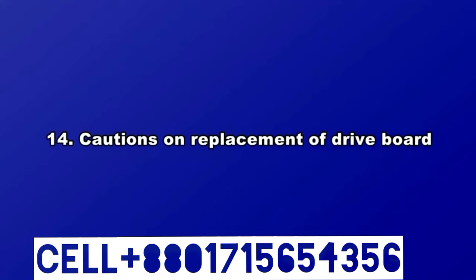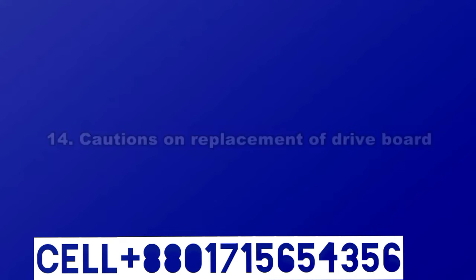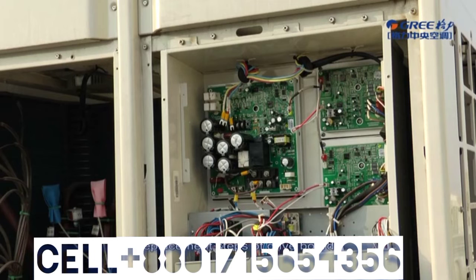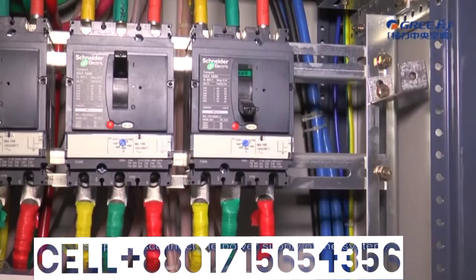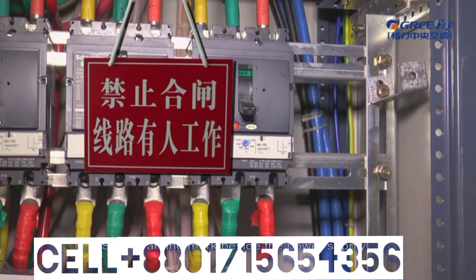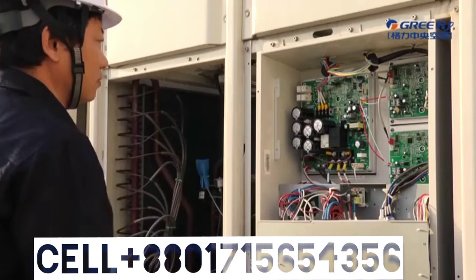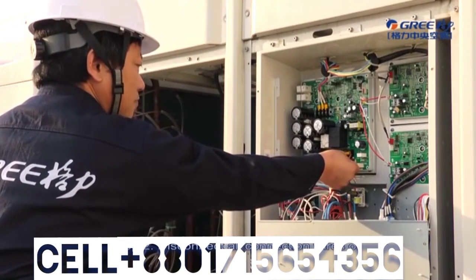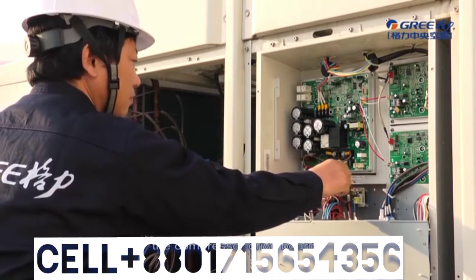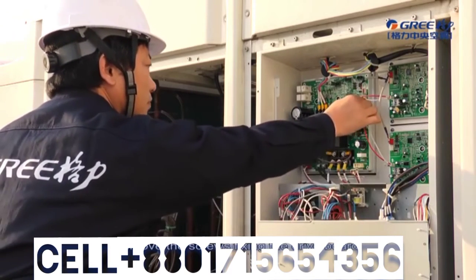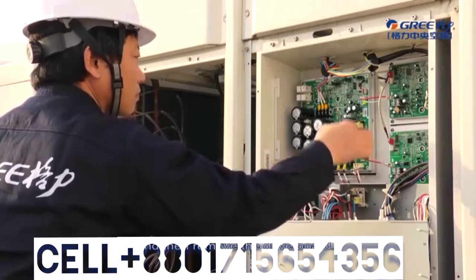14. Cautions on replacement of drive board. Replacement steps of drive board. Step 1. Disconnect the power supply of the system. Make sure the unit has been powered off for at least 20 minutes before operation. Set a warning mark beside the power supply. Step 2. Disconnect all connection wires of the compressor drive board. Remove the screws fixing the drive board and then remove the drive board.